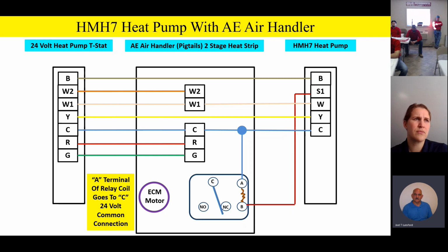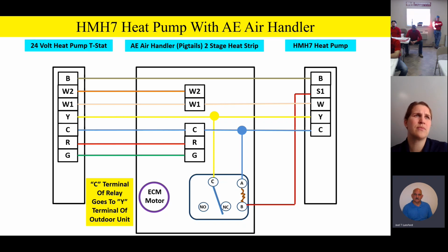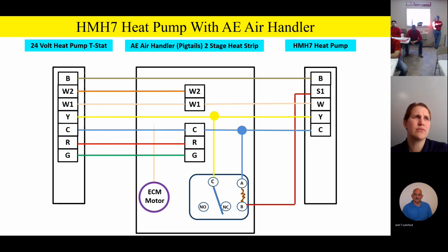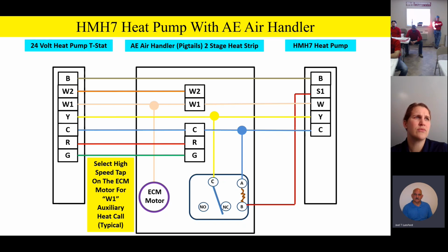So the actual contacts themselves on the relay, what we're going to do is take 24 volt from the Y terminal, and we're going to take that down to the common switching terminal on the relay. So we're feeding power to the common of the relay anytime we have power to the compressor outside, or anytime we have a compressor call on Y. Then on the ECM motors, as we start wiring that ECM motor up, we're going to take the high speed tap off that ECM motor and take it up to the W1 input. Now, the reason we do that is we want to make sure that anytime we have an auxiliary heat call, we're going to drive that fan to high speed. And this is very typical that you'll see most of the time. Your high speed tap is going to be for your auxiliary heat call. That way you don't overheat the heat strips and so on.